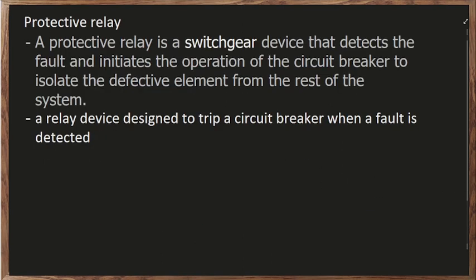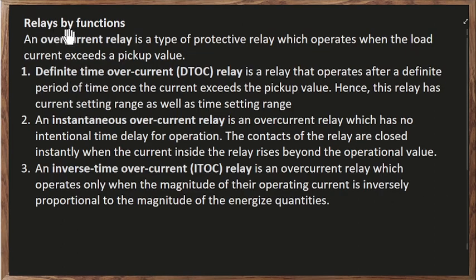Okay. So speaking of transmission lines, the transmission line must be protected, so we have the protective relay. A protective relay is a switchgear device that detects fault and initiates the operation of the circuit breaker to isolate defective element from the rest of the system. Now, a relay device designed to trip a circuit breaker when a fault is detected. So kaya tinatawag siyang protective relay, no? Okay. So relay by function, there are different types of relay by function.